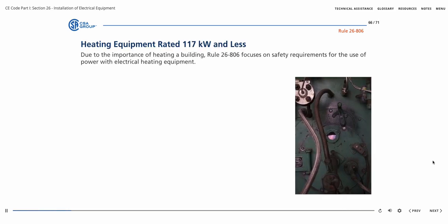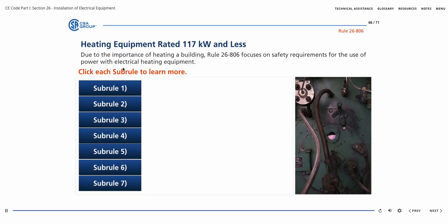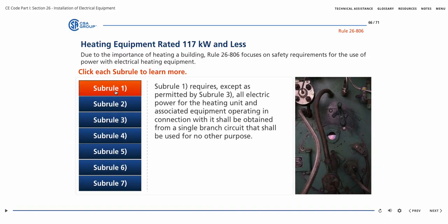Due to the importance of heating equipment in a building, Rule 26-806 focuses on safety requirements for the use of power with electrical heating equipment. Sub-Rule 1 requires, except as permitted by Sub-Rule 3, all electric power for the heating unit and associated equipment operating in connection with it shall be obtained from a single branch circuit that shall be used for no other purpose.